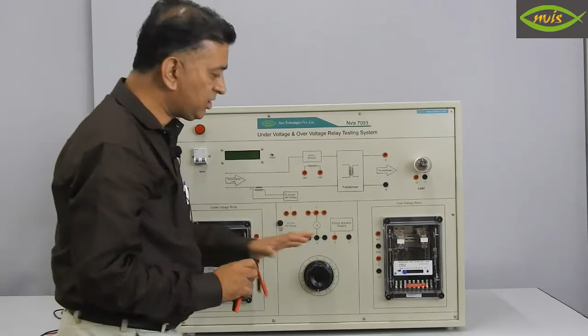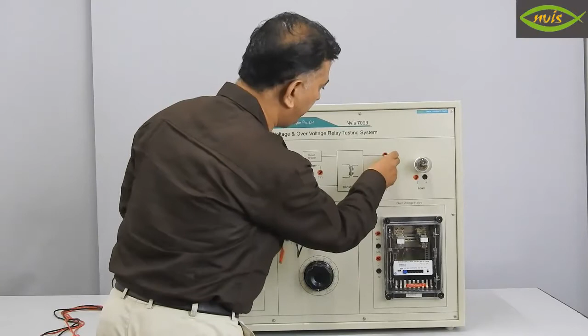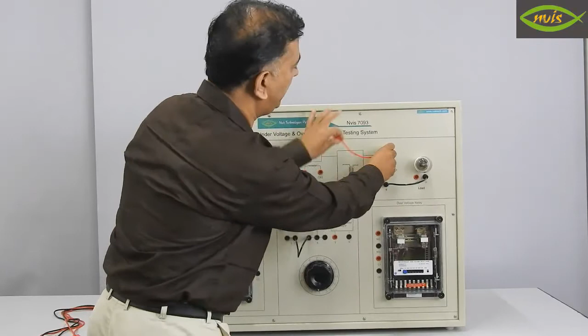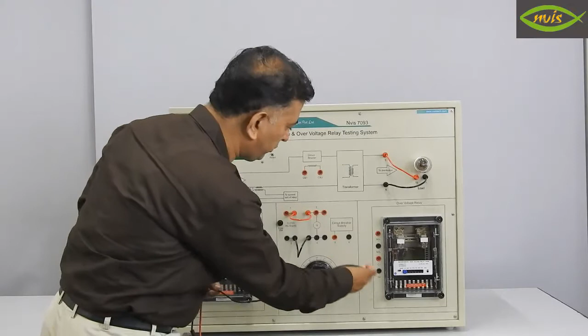So we'll make its connection. The connection is also very similar to the under voltage relay system we did in the last experiment. First we will connect the power supply to the voltmeter, so that the voltmeter can display the voltage. And the load also is required to be connected. On the transmission line, as I explained in the previous experiment, the load is connected. Now we will make the connection of the relay coil. These C1 and C2 terminals are the relay coil terminals. The operating voltage must be fed to these coil terminals. So the relay coil terminals are connected with the supply. This is the supply which is given to the voltmeter as well as to the relay coil. These are very simple up till now.